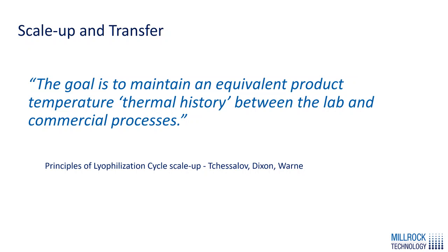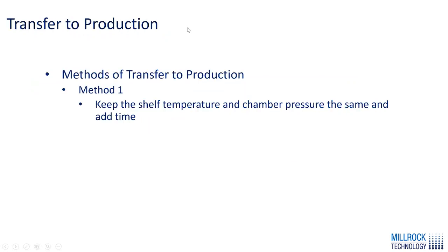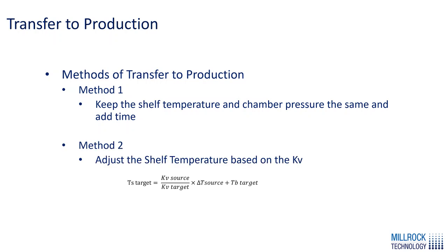For scale-up and transfer, the goal is to maintain an equivalent product temperature or thermal history between the lab unit (the source) and your commercial process (typically production). There are two consistent transfer methods: first, keep the shelf temperature and chamber pressure the same and add about 30% time to the primary drying cycle. Second, adjust the shelf temperature based on the known KV values for the source in the lab and the target in production. There is a quick equation showing how the shelf temperature is adjusted based on the KV of the two systems.